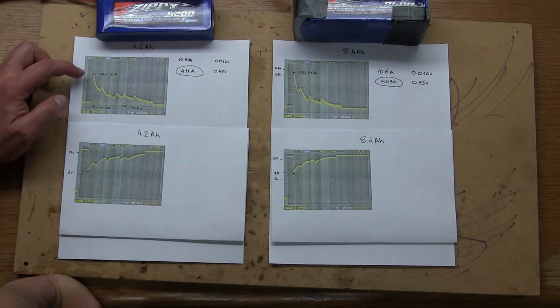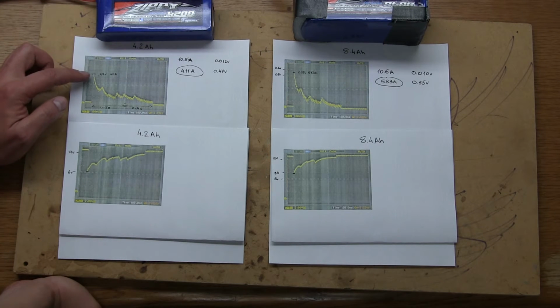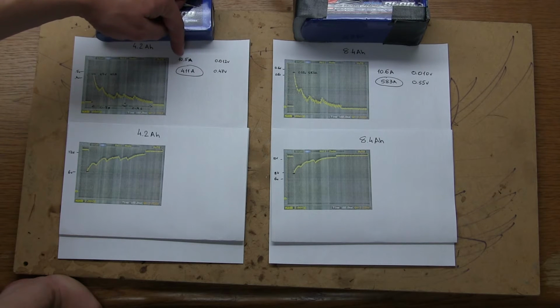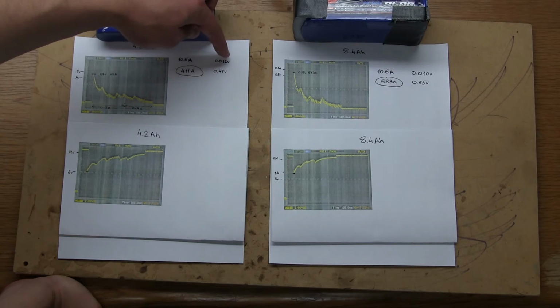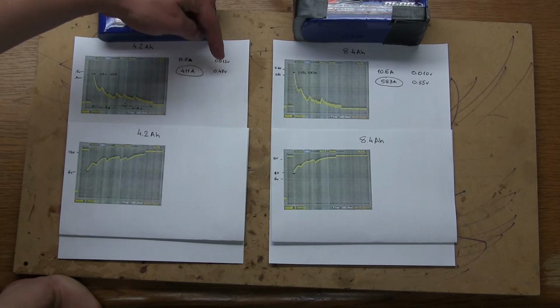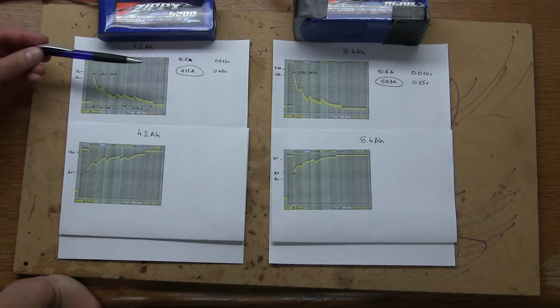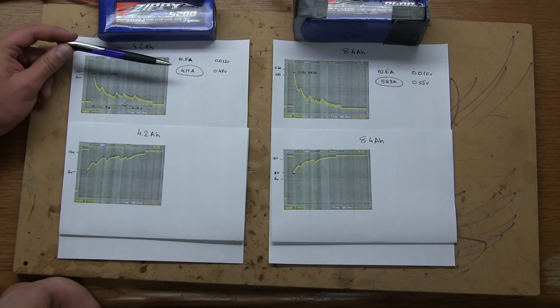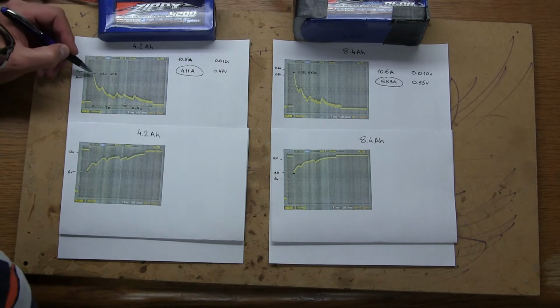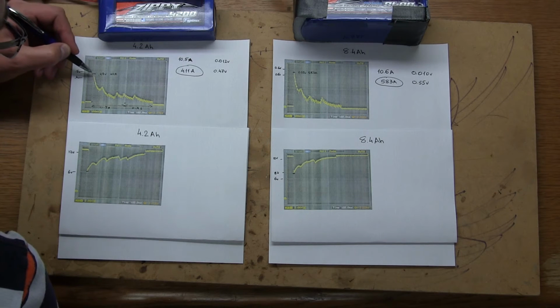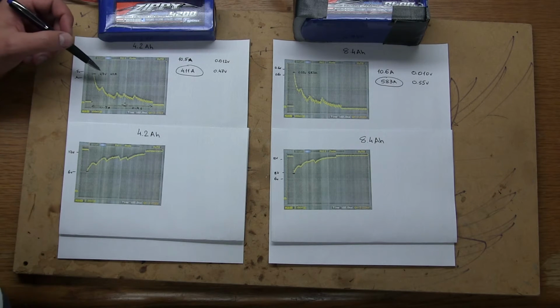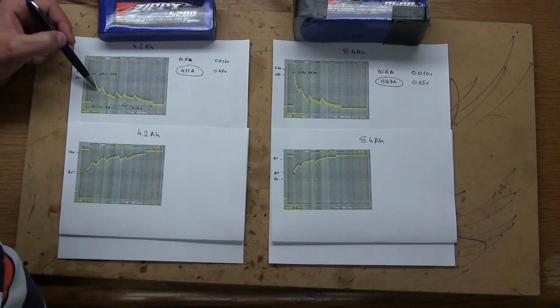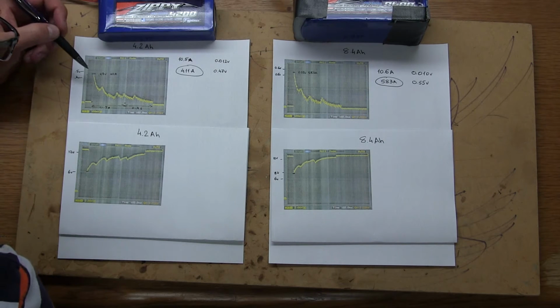The peak voltage drop across the positive lead was about 0.47 volts for the small battery, and our measurement was that 10.5 amps corresponds to 12 millivolts. We measured 0.47 volts of voltage drop here, and I calculated it's 411 amps. So at this point it's 411 amps, which is pretty much, as far as I understand, the short circuit current of this battery.